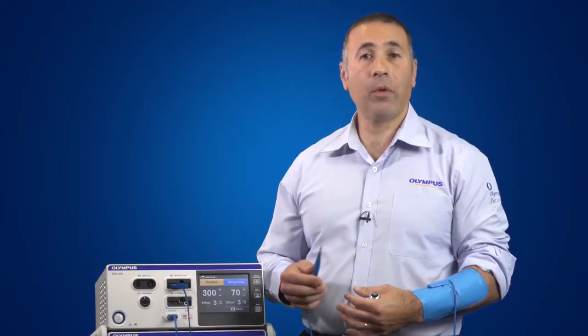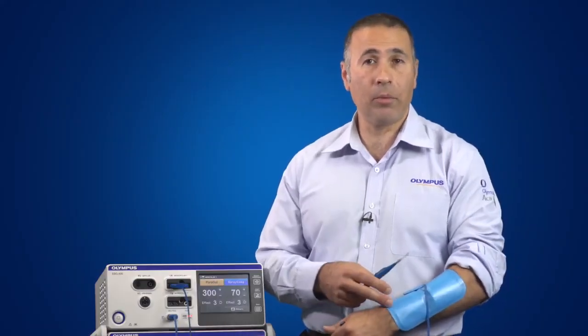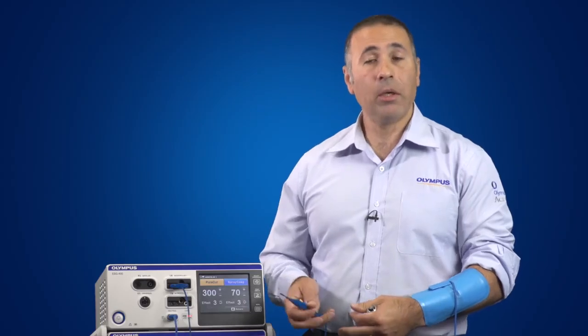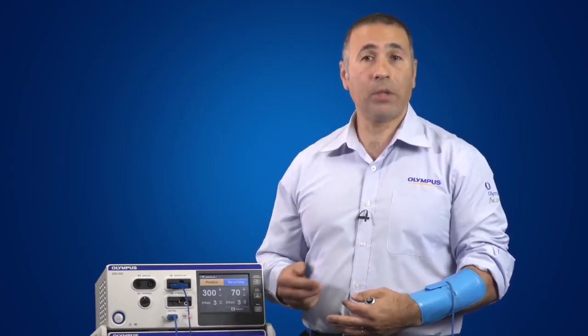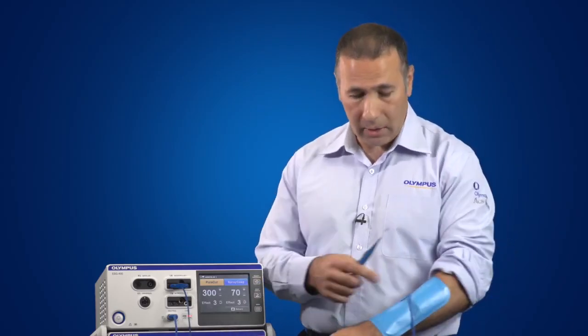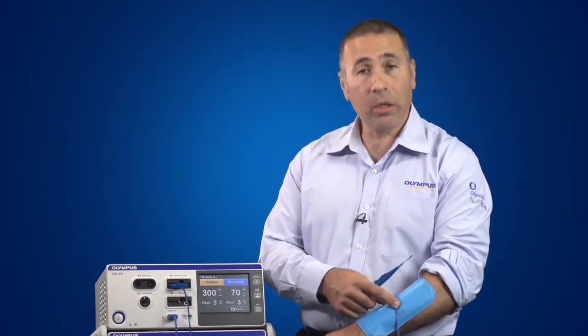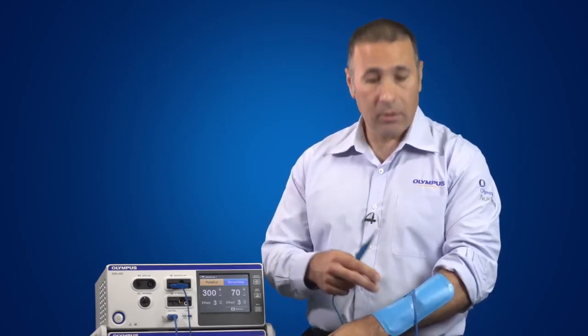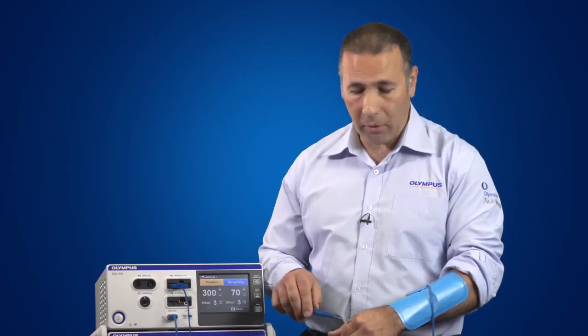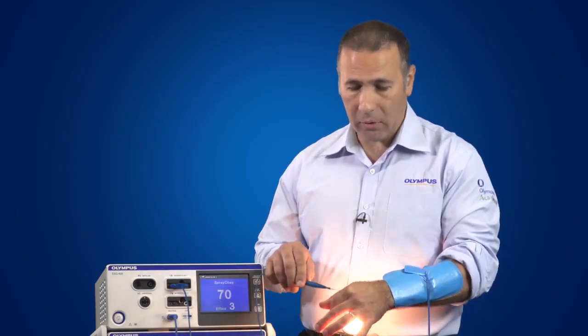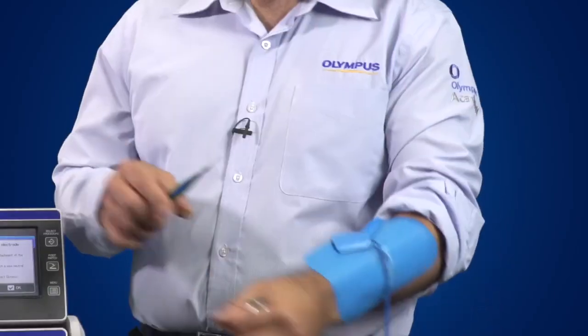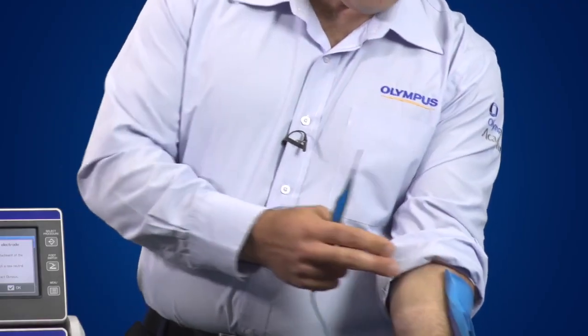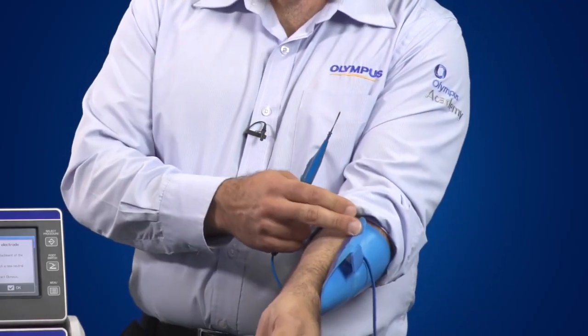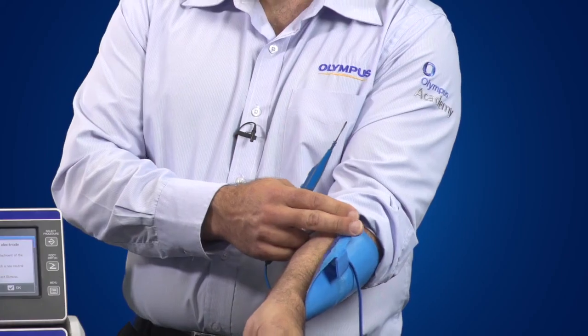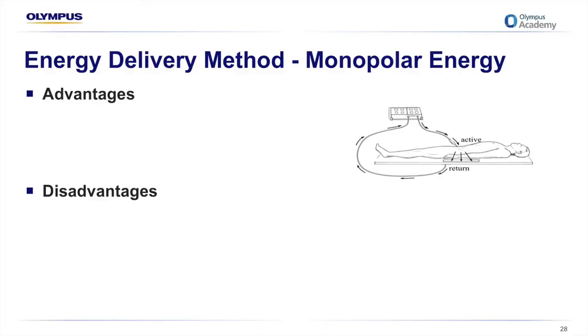So in order to overcome those patient return electrode site burns, I'm going to demonstrate to you a generator that's equipped with contact quality monitoring. As the quality of the contact of the plate to the patient interface is compromised, the generator will deactivate. So you can see there, only a small component of the plate has come off me as the patient.